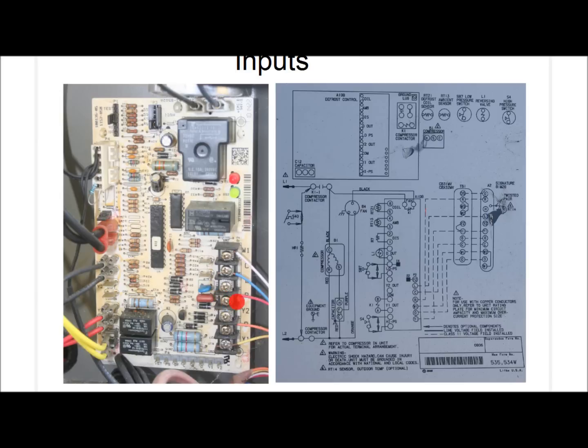Then we have the R terminal. Now the R terminal is a constant 24 volts. It is the power to the board. Our power lights are on here, and it also provides power for the microprocessor that controls the defrost timing and so forth on the control board.